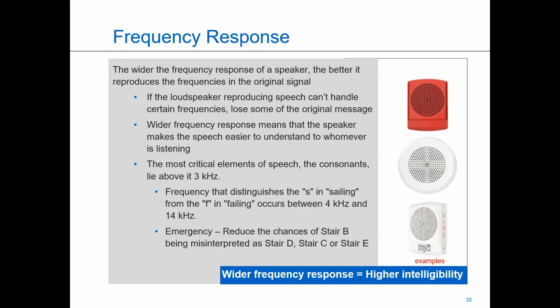That's a code that changed a few years back, where it's a lower frequency sound for sleeping rooms. I don't have to get into it, but that frequency response needs to be handled by a speaker, either a product that can handle that tone completely, or something that can generate the low frequency tone, and that the speaker can play it properly. So frequency response is important.